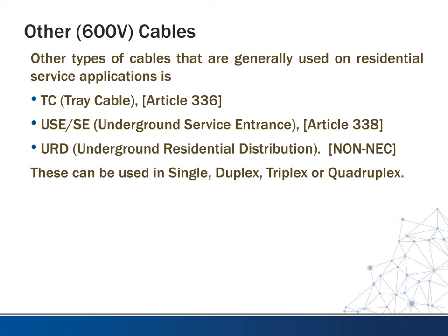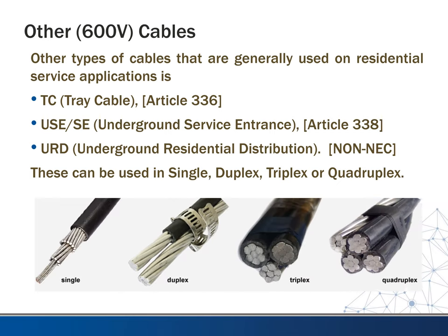The bottom two — USE, SE, and URD — usually come in the form of single, duplex, or triplex assemblies. If you hear people talking about triplex or duplex, this is what they mean. They are combined in an assembly on one spool so you can pull them all at one time. Usually you'll have the neutral or ground conductor, which will be bare, and then your phase conductors, which will have insulation on them.